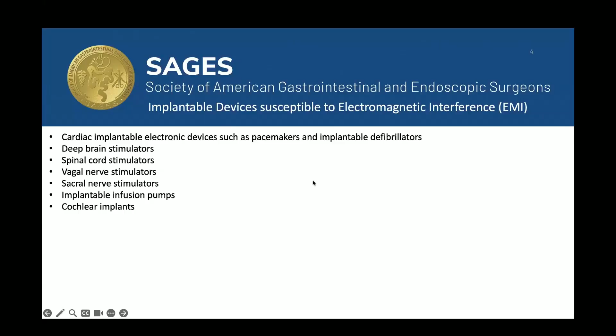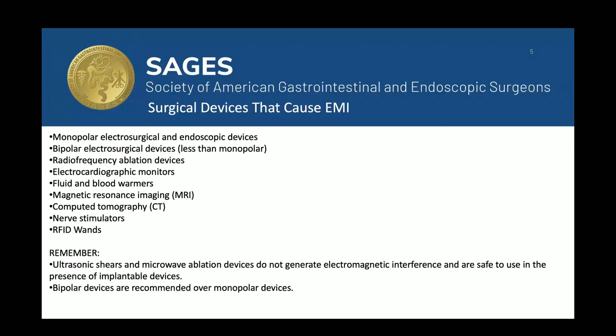In terms of devices that cause interference, top of the list is monopolar energy, for standard surgical instruments, laparoscopic instruments, and the endoscopic instruments, which we don't usually think about. Then bipolar instruments have less of an effect. Radiofrequency ablation devices also have an effect. Technically, EKG monitors, RFID devices, and fluid and blood warmers can have a small current. A lot of these smaller issues are negated by more modern devices with appropriate shielding, but it's worth remembering these things, and always MRIs. Another reminder: ultrasonic devices and microwave ablation do not generate EMI, so they're safe to use. And bipolar is always recommended above monopolar when it's appropriate.